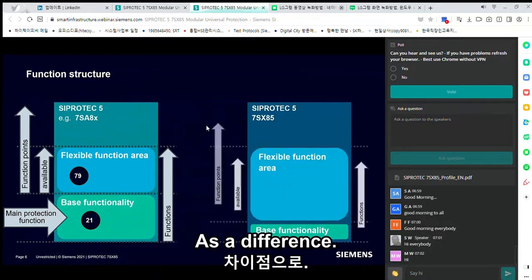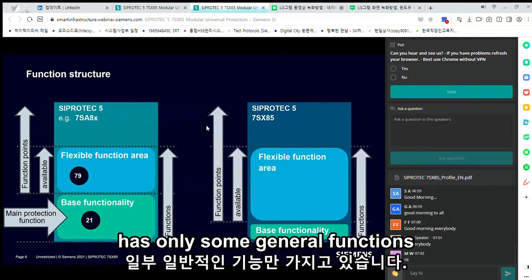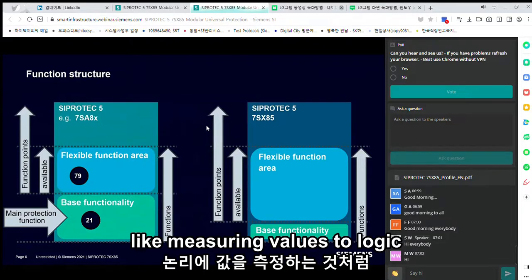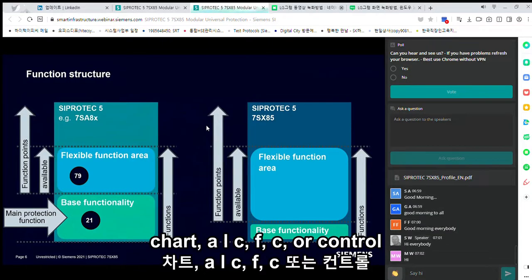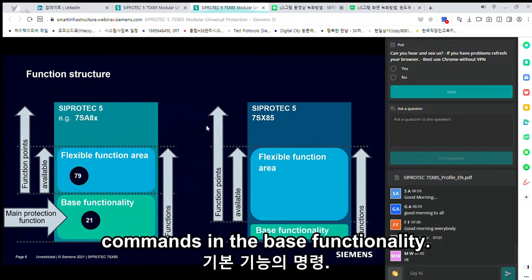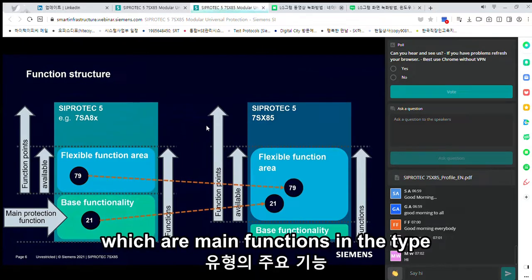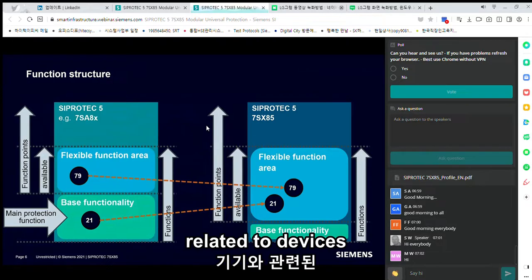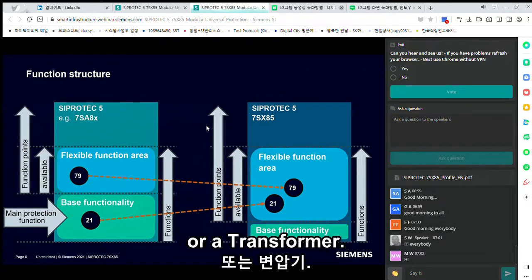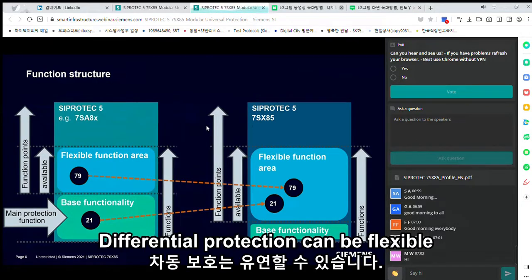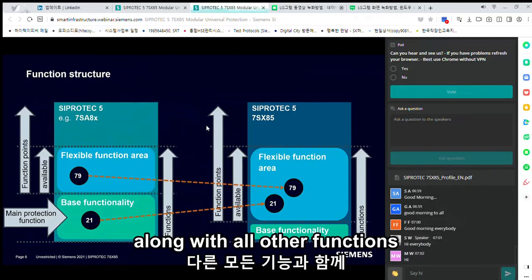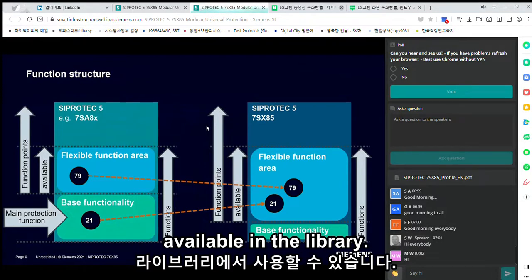As a difference, the universal device has only some general functions like measuring values, the logic chart editor, CFC, or control commands in the base functionality. The functions which are main functions in the type-related devices, such as distance or transformer differential protection, can be flexibly added along with all other functions available in the library.